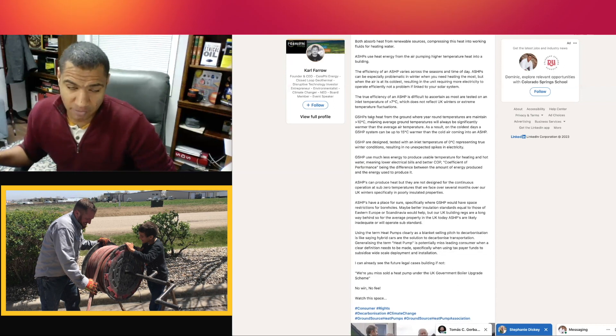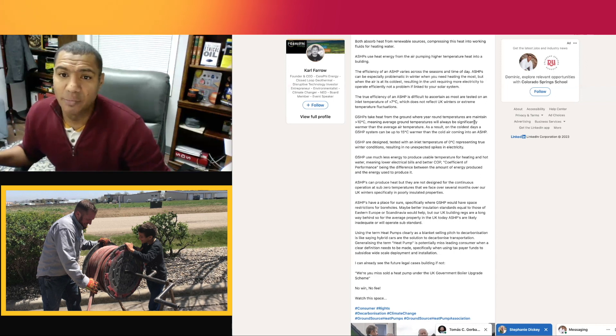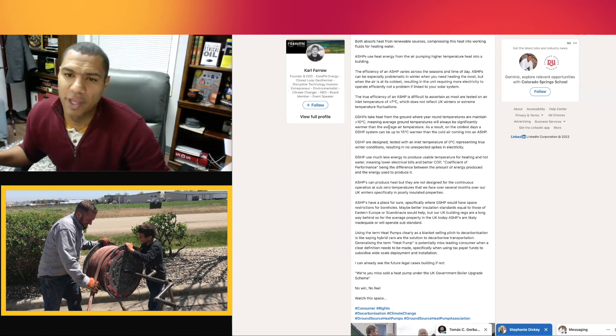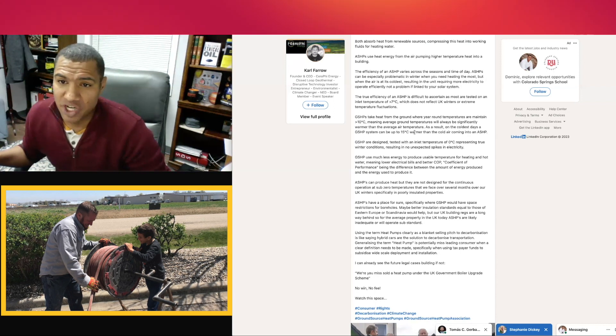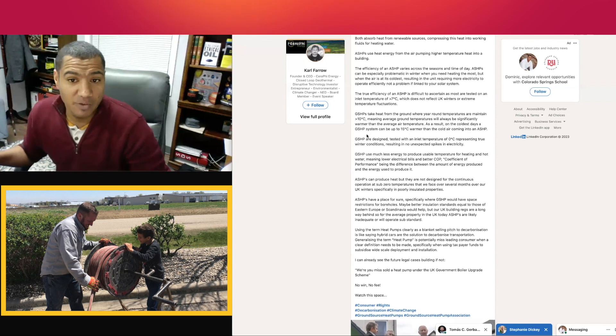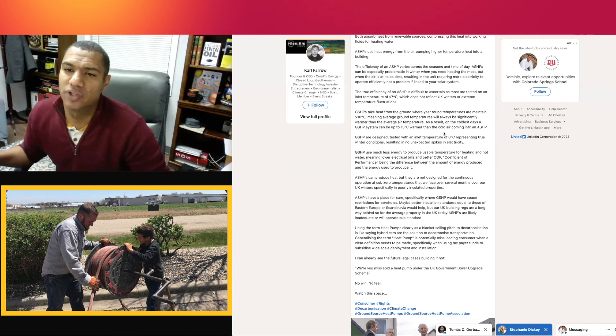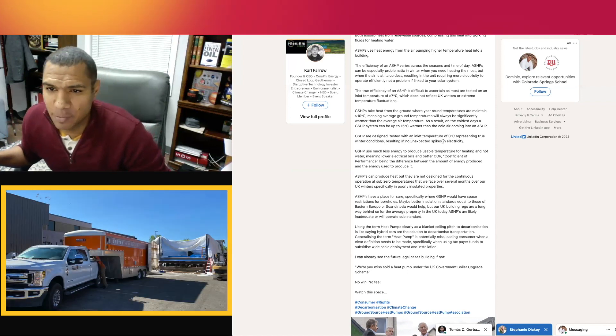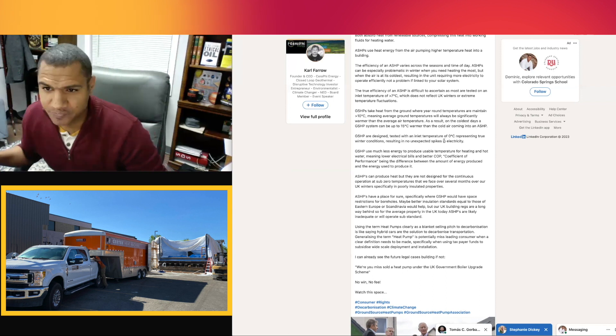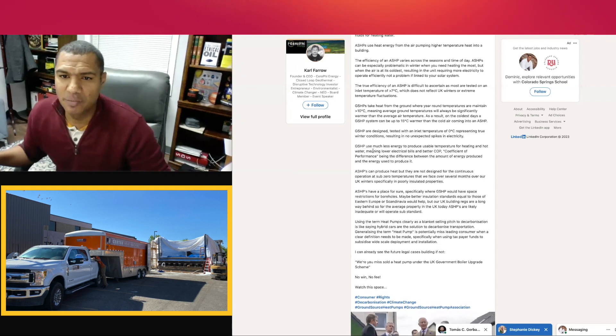Farrow explains: 'Ground source heat pumps take heat from the ground, where year-round temperatures are maintained at above 10°C, meaning average ground temperatures will always be significantly warmer than average air temperature. As a result, on the coldest days a ground source heat pump system can be up to 15 degrees Celsius warmer than the cold air coming into an air source heat pump.